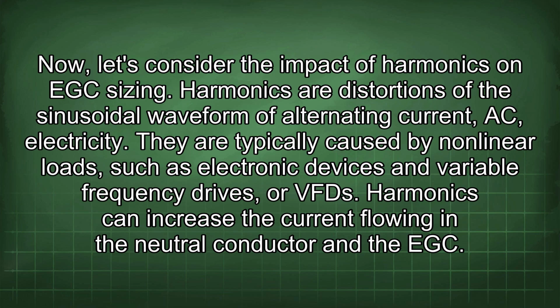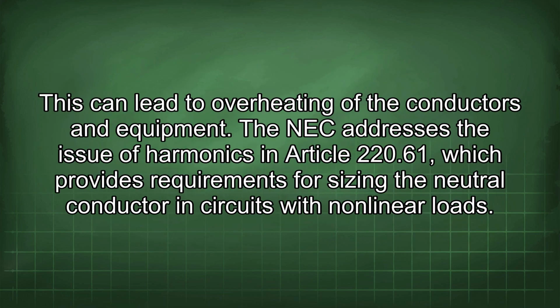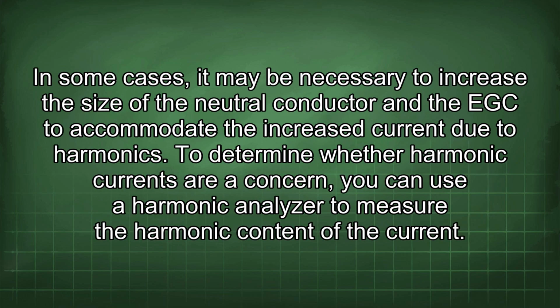Harmonics are distortions of the sinusoidal waveform of alternating current, AC, electricity. They are typically caused by nonlinear loads such as electronic devices and variable frequency drives, or VFDs. Harmonics can increase the current flowing in the neutral conductor and the EGC. This can lead to overheating of the conductors and equipment. The NEC addresses the issue of harmonics in Article 220.61, which provides requirements for sizing the neutral conductor in circuits with nonlinear loads. In some cases, it may be necessary to increase the size of the neutral conductor and the EGC to accommodate the increased current due to harmonics.